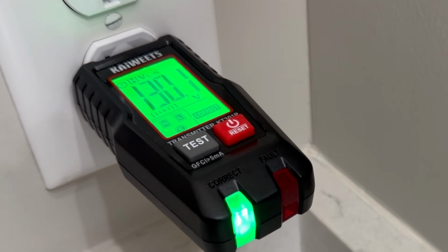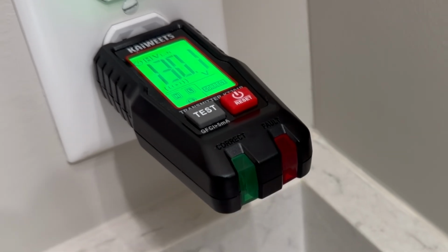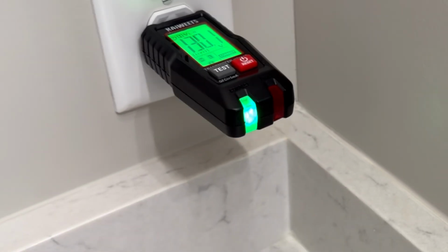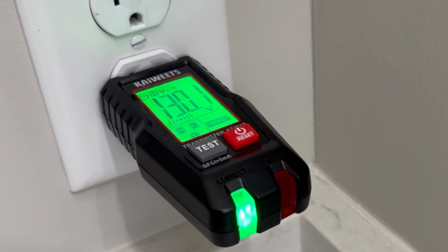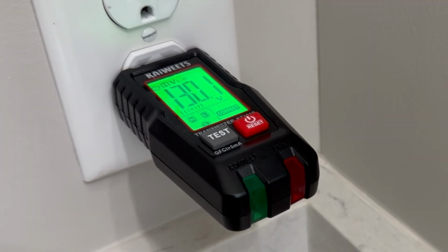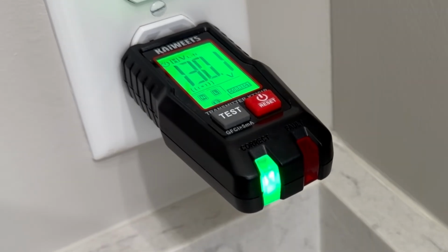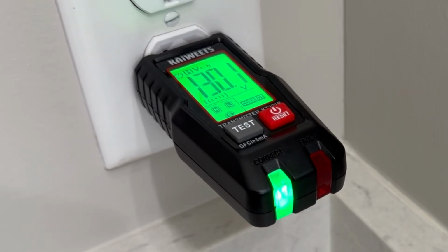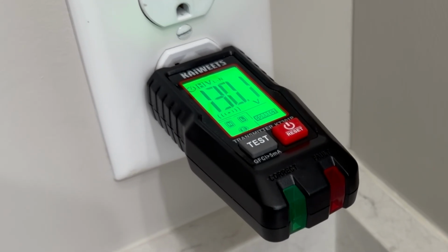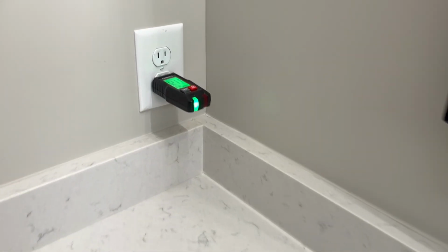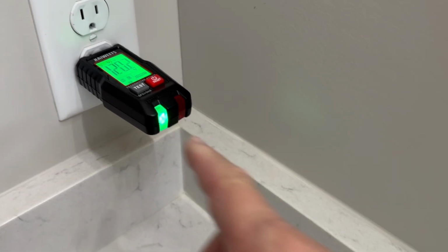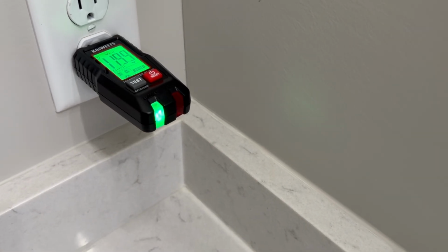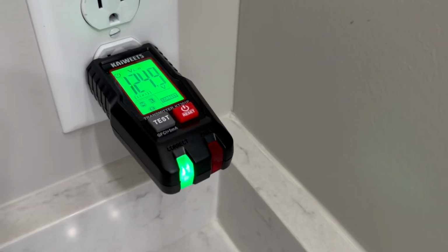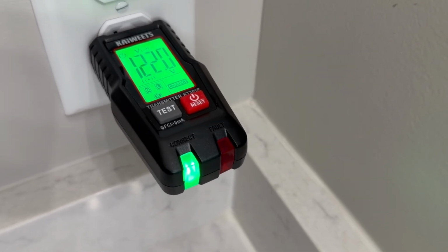It shows the previous volts, 130 volts. That's going to vary since it's alternating current. So what we can do, go turn the panel back on, and then this green light should turn solid to indicate voltage has been returned. So let's go turn the panel back on. Turn the breaker back on. Okay, return back to the transmitter, and you can see that the indicator light is solid green, indicating there's voltage. And you can see the voltage varying there.